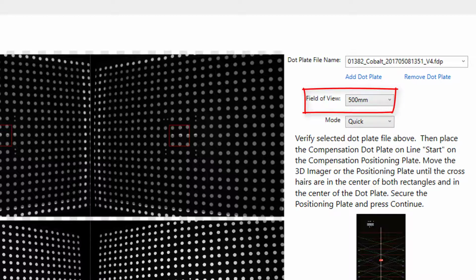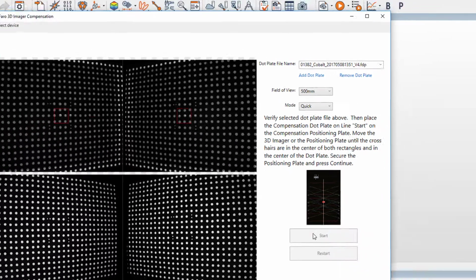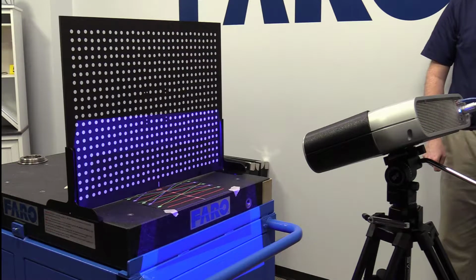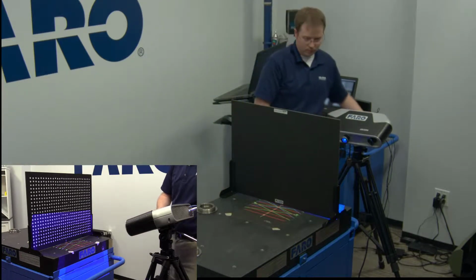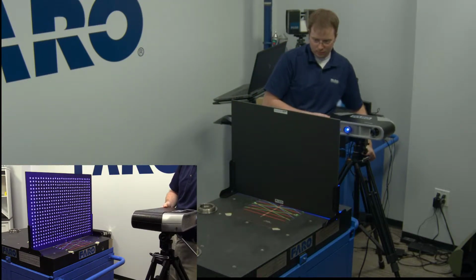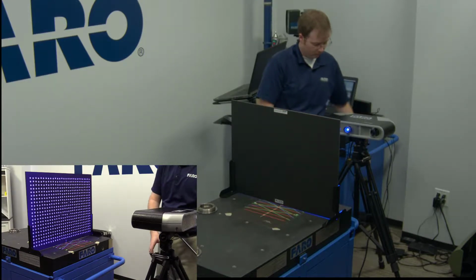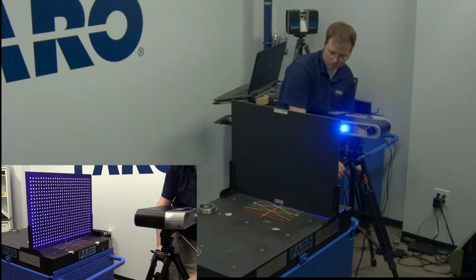Next, verify that the correct lens volume is chosen. Lastly, choose either Quick Mode or Full Mode for the compensation routine. Quick Mode allows for the compensation to be performed at an abbreviated number of positions. However, no accuracy is lost. At this point, the Cobalt's crosshairs have been activated and can be used to place the Cobalt in the correct position for compensation. First, make sure the Cobalt is level and is facing directly at the compensation plate. Then, place the Cobalt so that the crosshairs are directly in the center of the dot plate.